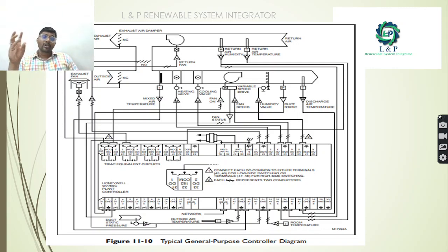Okay, and most importantly, all these valve actuators, chilled water valve actuators, damper actuators, all these things come under the category of the analog output signals, which are being commanded by these DDC controllers. And even exhaust fans also. In the fan also we are monitoring so many statuses, that is on/off status, trip status, fault status. Each and everything we will be controlling.